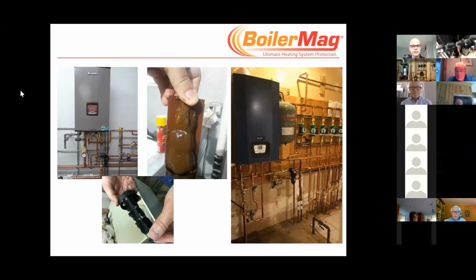Here's some pictures. The top left one, you'll see a nice Lochinvar boiler there with a BoilerMag on the return. I believe that's from your area. On the right hand side, this is up in Alaska. Brand new copper pipe system with a Dunkirk boiler. The picture at the bottom in the middle with the contamination on the magnet, that's what the magnet looks like when you take it out. That's from the installation on the right hand side after 2 weeks. So they installed it, ran it for 2 weeks, checked the magnet, that's what they took out of it.